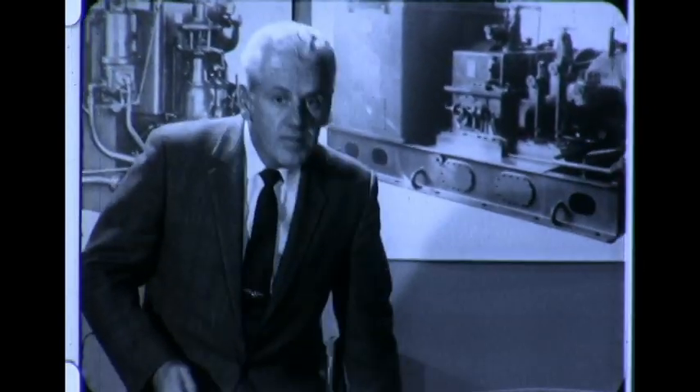Could you tell us a little bit about the turbine itself? Certainly. These are high-speed turbines. They develop anywhere from a few hundred up to more than 15,000 horsepower, and they operate at speeds up to 12,500 RPM, or even higher for some applications. The amount of precision that goes into the manufacture of these turbines is very, very high. Our production people could tell you a lot more — would you like me to give them a buzz? Why, yes. Thanks very much.